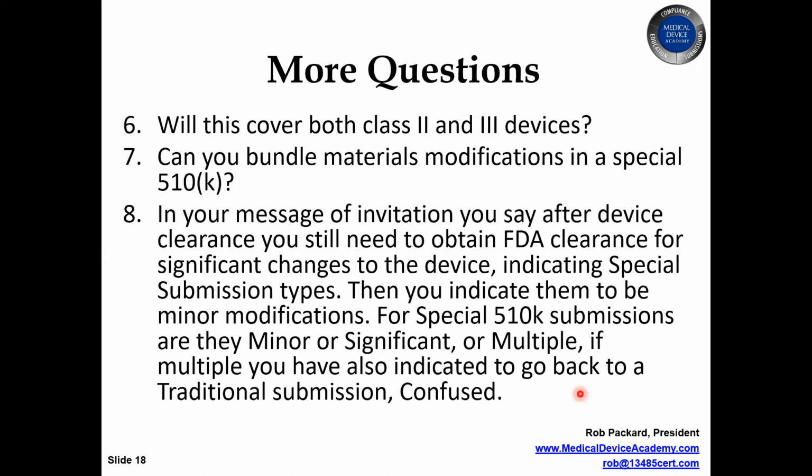Number 7 question, can you bundle material modifications in a special 510K? I will give an example of one where they made multiple changes, but they were all mechanical changes. They weren't changes to the materials that would affect biocompatibility.